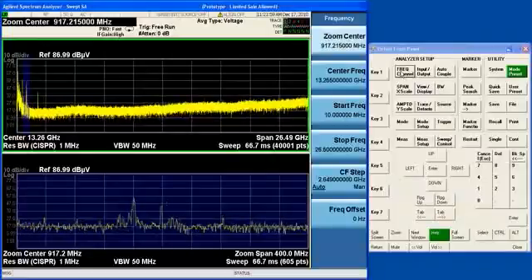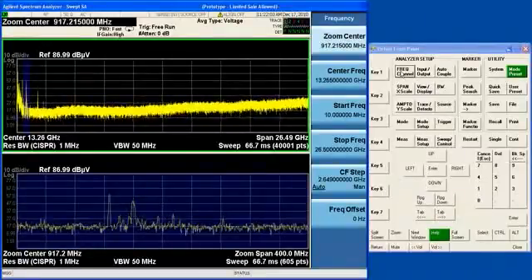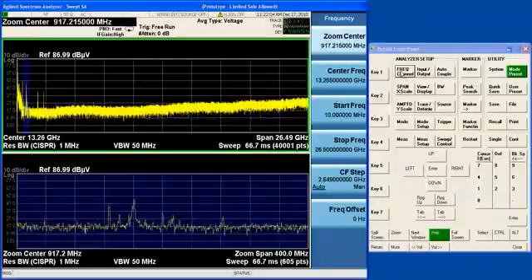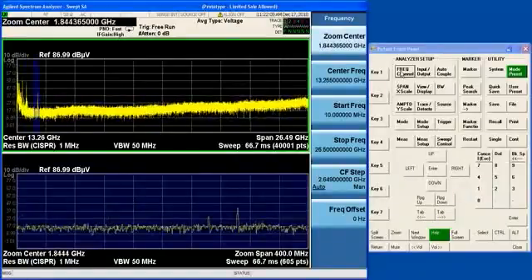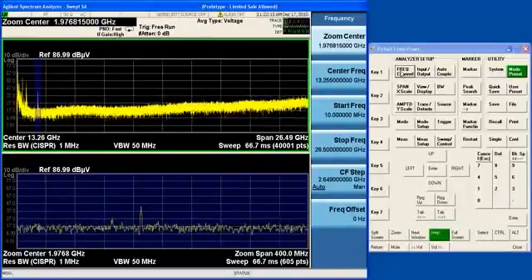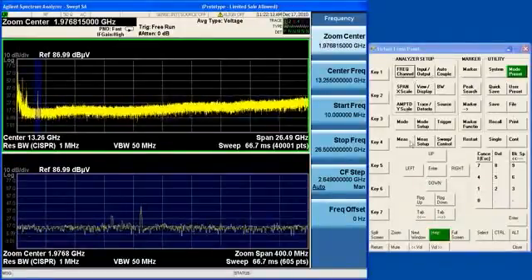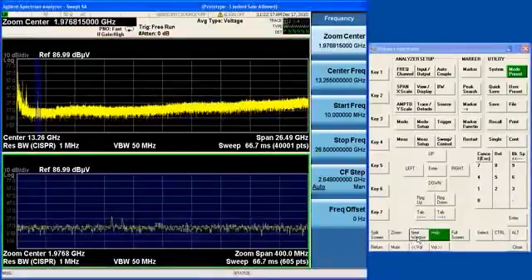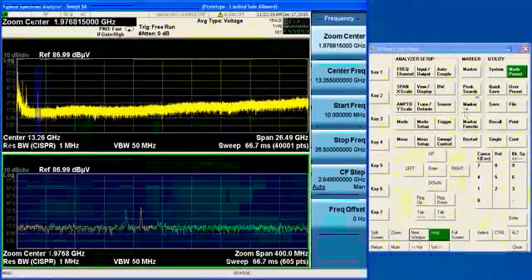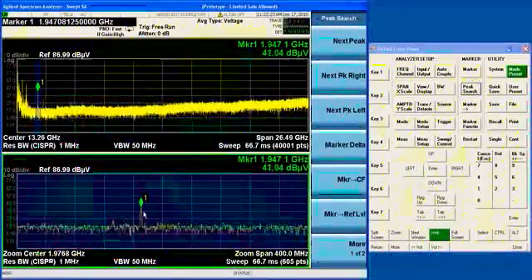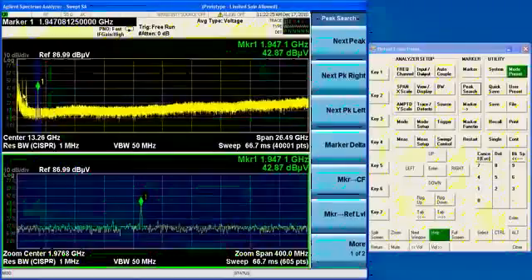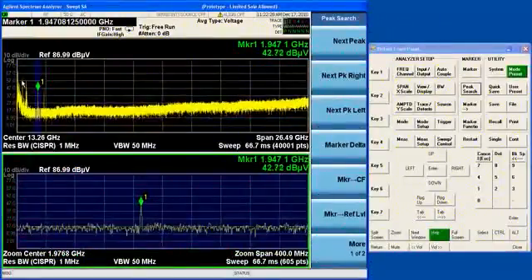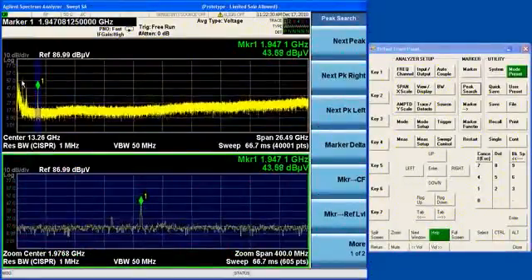Now there's one thing that's very special about the zoom region, and that is that if you do a peak search while the focus is on this region, the peak search will be confined to that region. So let me go back down to the lower window. Now I'm on the lower window. I do a peak search, and it's finding the peak in the lower window, even though there are peaks in the upper window that are clearly higher than the peak in the lower window.